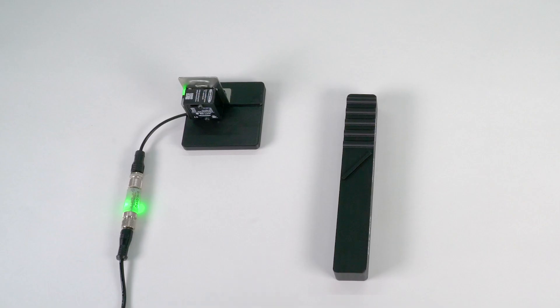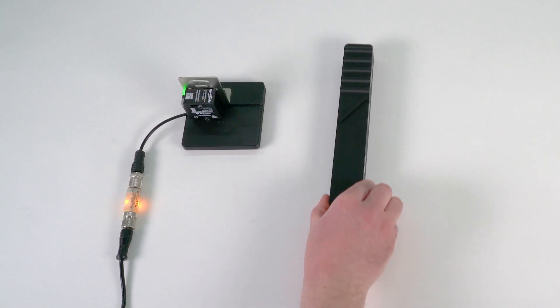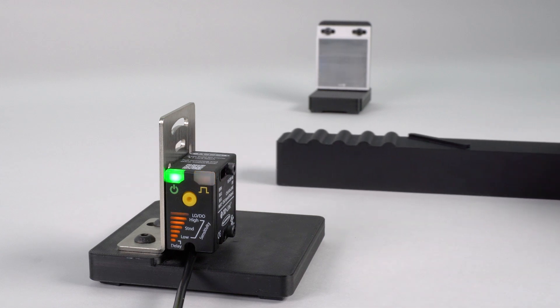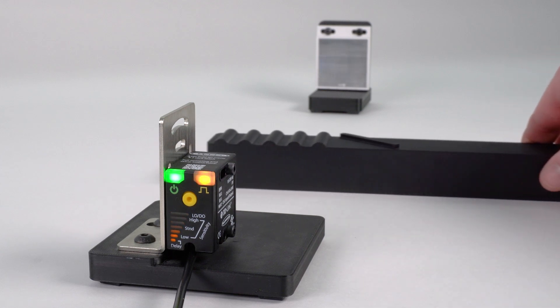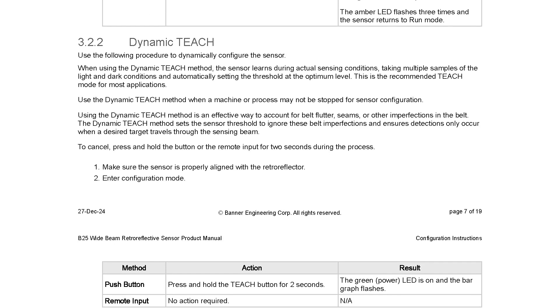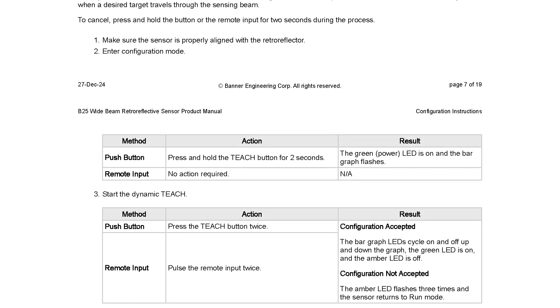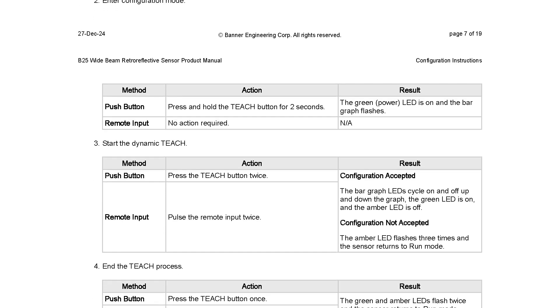If your application has an inconsistent beam obstruction when no target is present, such as flutter from a moving conveyor belt, a static teach may cause the output to chatter as the obstruction moves. To counter this, you can perform a dynamic teach which takes multiple samples of light and dark conditions and automatically sets the threshold at the optimum level.